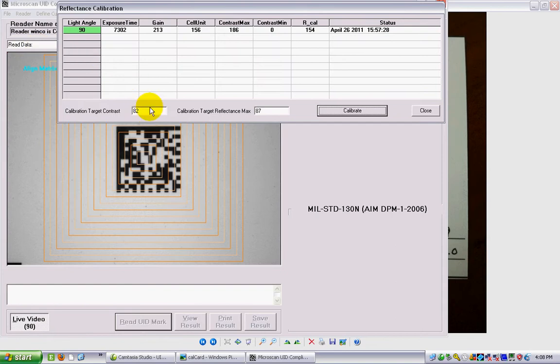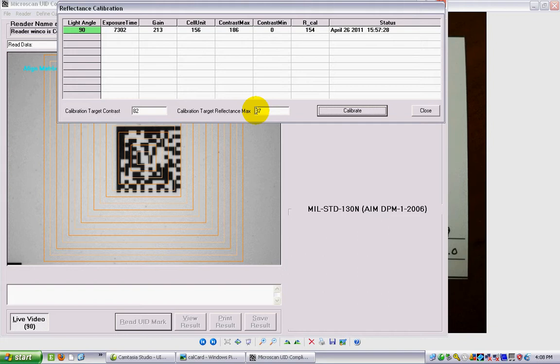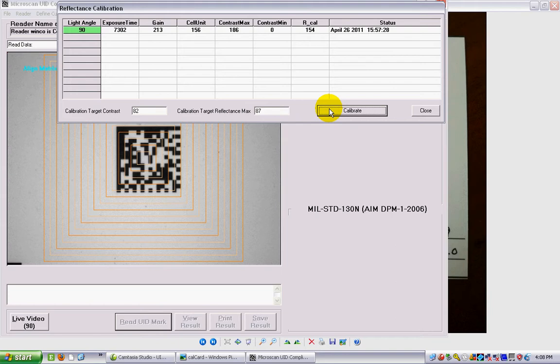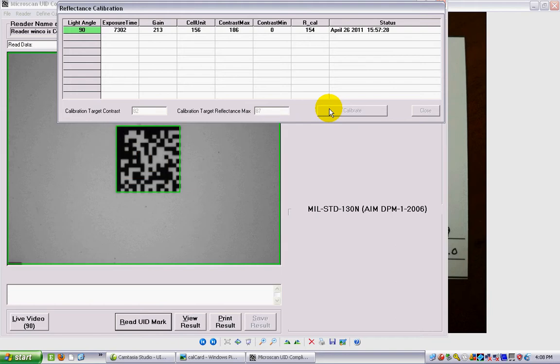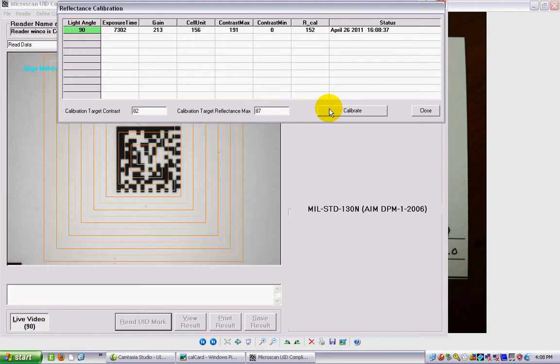Now, these two values here, the contrast and the maximum reflectance, are handwritten on the card. They're usually a decimal number. I usually put the closest whole number to that. I just type them into the boxes and I click calibrate. A couple more beeps, the light on the reader goes on and off a bit, and it's basically done already.